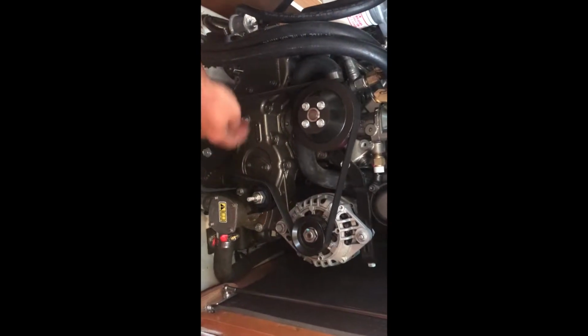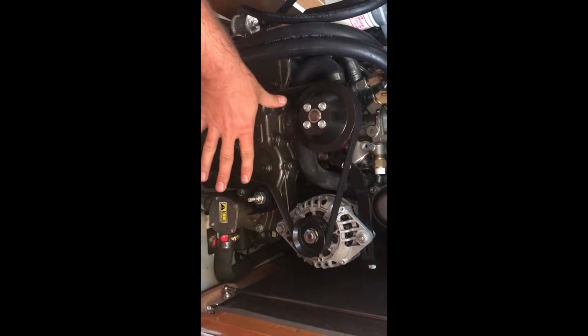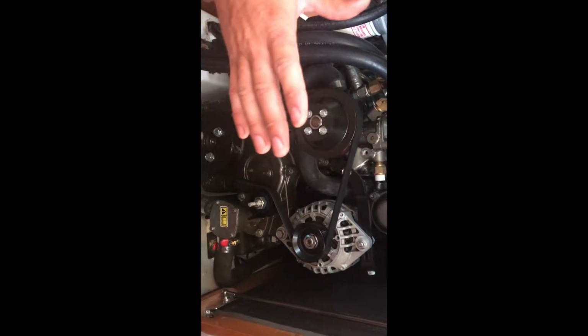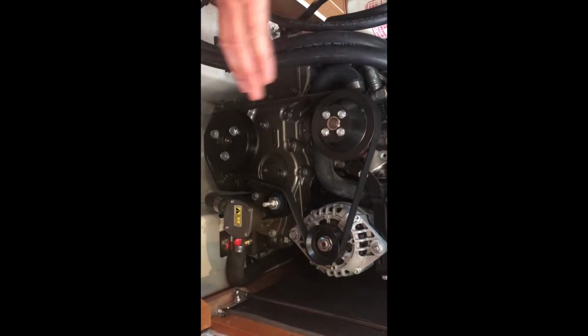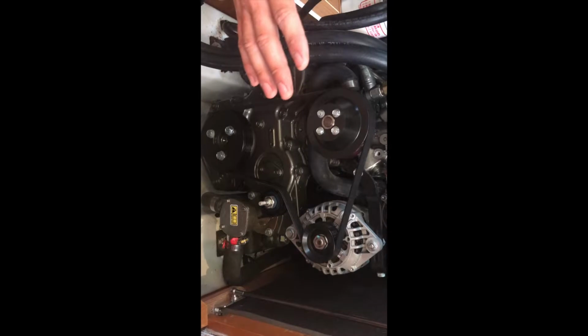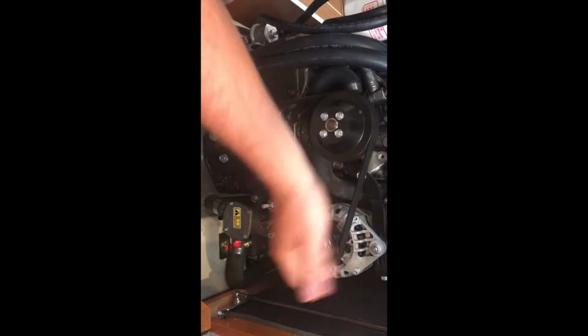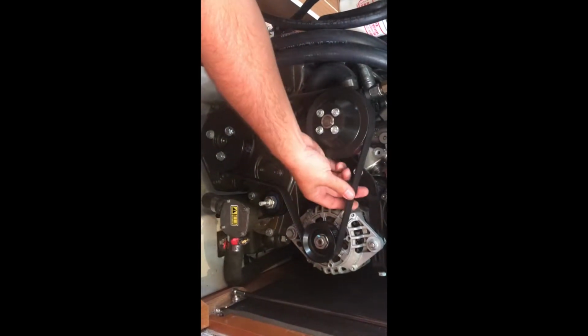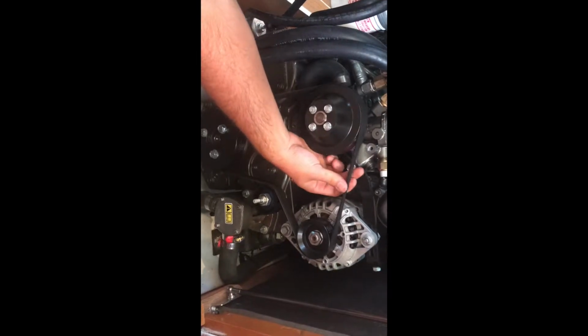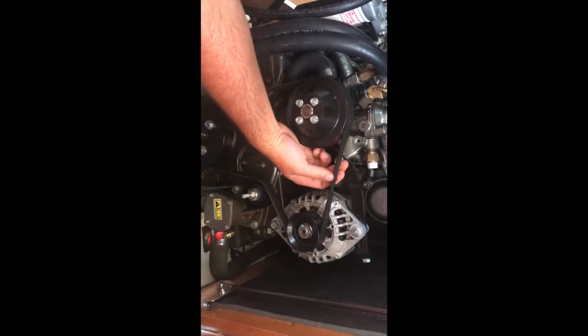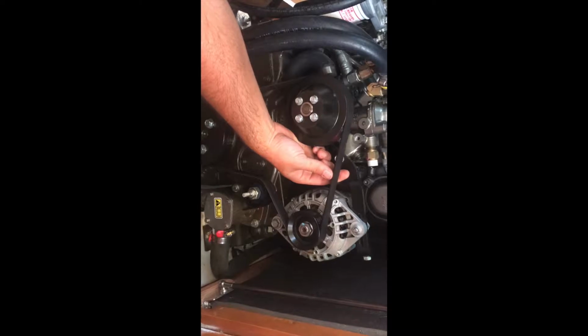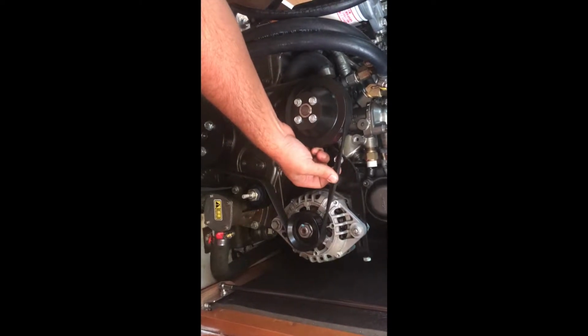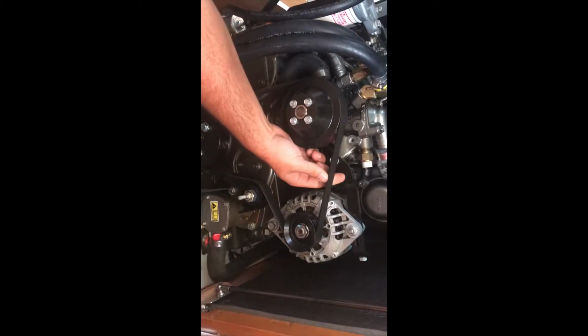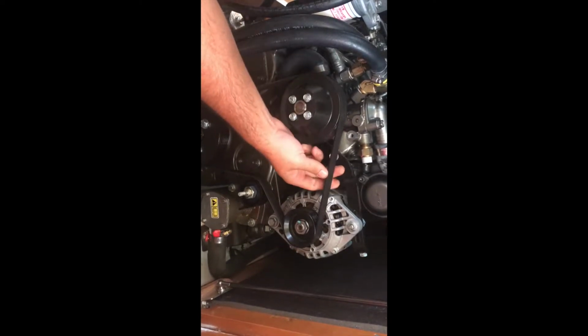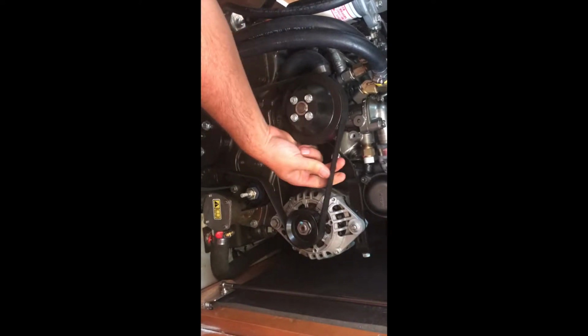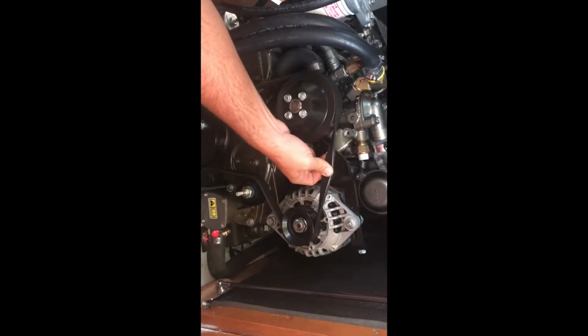Then you just take it off and put the new belt on. Take a picture of it so you know how it all goes, because this looks simple, but once you take it all off, sometimes people get confused. So take a picture, loosen it off, and put the new one on. Then when you put it on, the tightness is kind of a feel thing, but the belt should only be able to go partially up like that. If it goes further, it's too loose—halfway is what you're shooting for in tension.